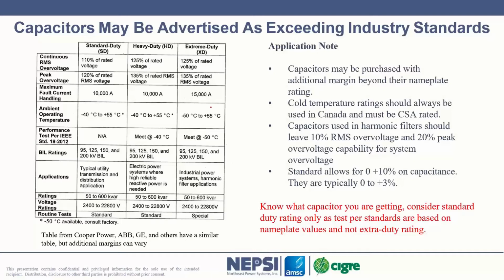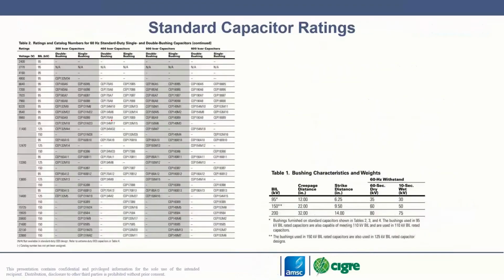Capacitor manufacturers oftentimes have what's called standard duty, heavy duty, extreme duty. Do know that these values change from one supplier to the next, so you have to look at these values. I can tell you that a heavy duty capacitor from ABB is different than a heavy duty capacitor from General Electric or Eaton. They're just different. So understand the capacitor that you're picking, and make sure that you're applying it within its rating.